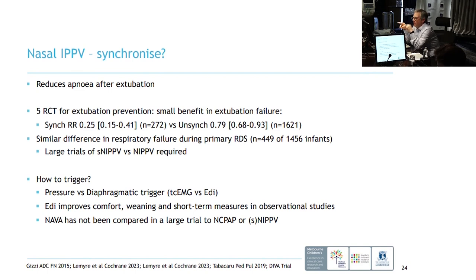Or they trigger directly off the diaphragm - if the diaphragm's moving, you assume the baby is breathing in. You can trigger off a transcutaneous diaphragm EMG, which now has a commercial version available, but it's not widely available and is generally used as a research device. Or you can trigger off electrical diaphragmatic activity measured from the esophagus using an esophageal catheter - that's NAVA. So essentially we have pressure triggers on most devices, and NAVA available on one at the moment.